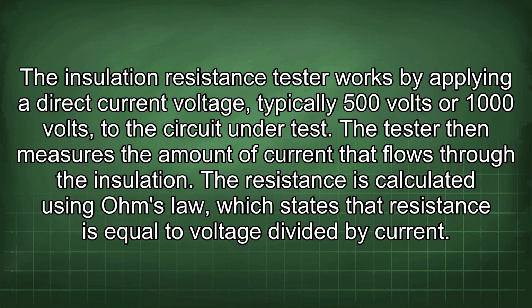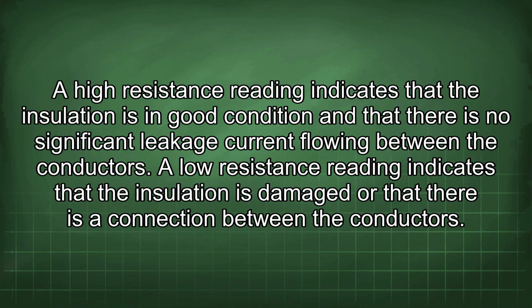The tester then measures the amount of current that flows through the insulation. The resistance is calculated using Ohm's law, which states that resistance is equal to voltage divided by current. A high resistance reading indicates that the insulation is in good condition and that there is no significant leakage current flowing between the conductors. A low resistance reading indicates that the insulation is damaged or that there is a connection between the conductors.